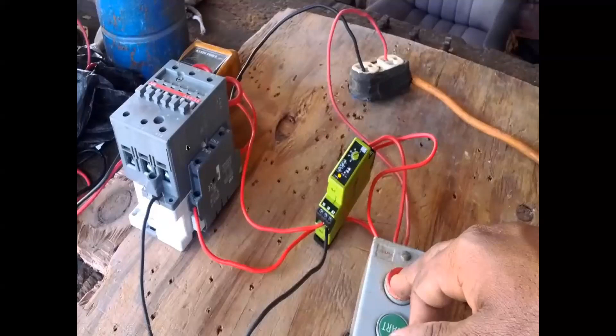What we require here is three phase. We need to turn on this relay or coil, and that coil should turn on after 10 seconds. So we require a timer here, situated in a field, with a timer knob. That knob can be set to 5, 10, or whatever seconds needed, and we send a power supply to the timer. It will start counting, and after the set time, say 10 seconds, it will turn on the coil.